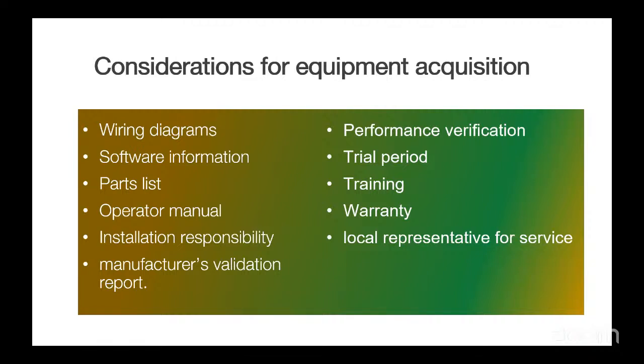There are some valves you don't even know what the valves are. But on the wiring diagram, it shows you valve 14 is the electrolyte flushing valve. This is so-and-so valve. That is what you call the wiring diagram. So if you have a wiring diagram of an equipment, maybe on your system, with that you can know what that thing stands for. Next, we talk about software information.